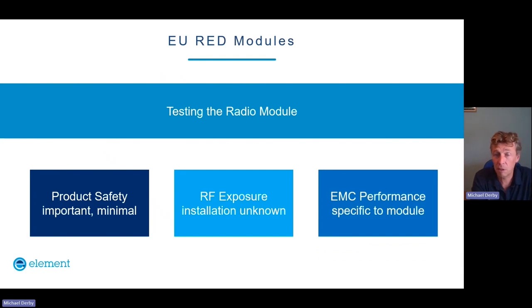EMC performance must be tested on the module. Now, there's a lot of the EMC tests you wouldn't want to do. You wouldn't want to do ESD directly to the bare board of a module. You could do the horizontal coupling plane and the vertical coupling plane, and of course the radiated immunity test. Some module manufacturers will put long cables on their test jig and do the fast transients and conducted tests, and others don't. There's no rules as such, other than the manufacturer's own risk assessment used to decide which tests apply to their radio.